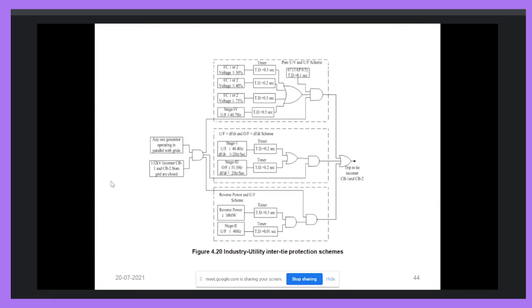Okay, how we design islanding protection. Okay, how we deployed the under voltage, under frequency, over voltage, over frequency relays for the protection of the system from the utility fault. Okay, that is called islanding protection.